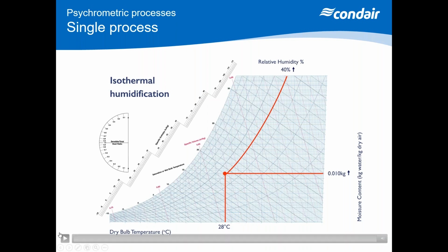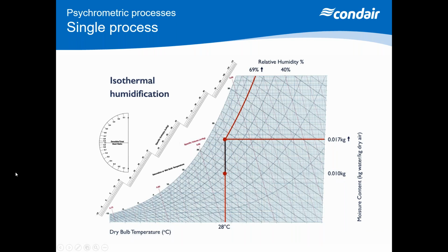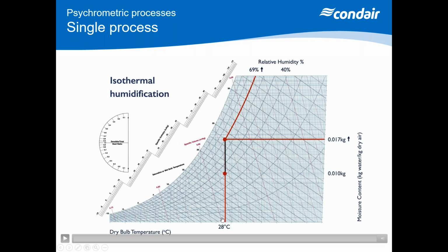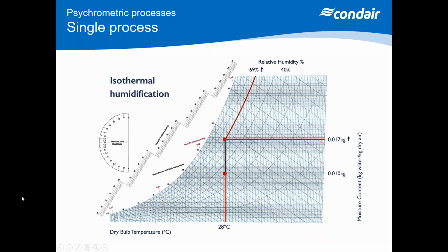So again, that process line is from my set point straight up to the condition that you require. And that's going to tell me a moisture difference. And we're going to need to know that moisture difference to do a duty calculation. So that's my isothermal: I need to preheat to my condition and then isothermally humidify up to my set point.